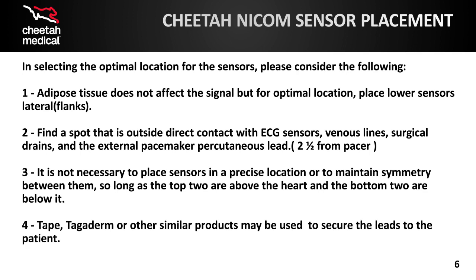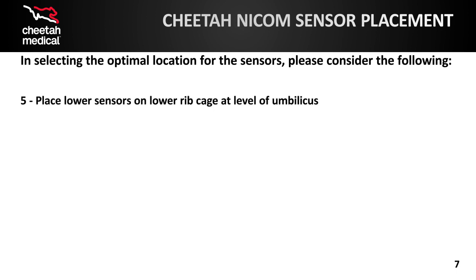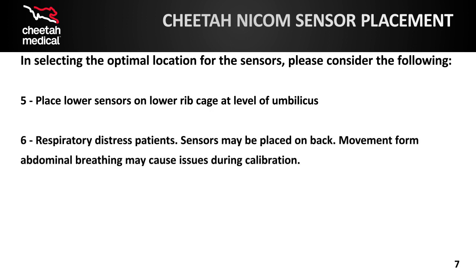When monitoring during anesthesia or for long-term periods, apply Tegaderm-type adhesive or other similar products to secure the lead in place. Also keep in mind the following when selecting optimal location for the sensors. 5. Place lower sensors on the lower rib cage at the level of the umbilicus. 6. Respiratory distress patients: sensors may be placed on the back. Movement from abdominal breathing may cause issues during calibration.